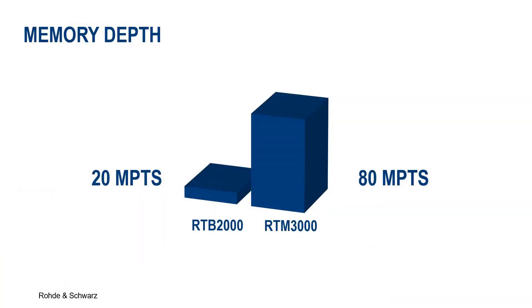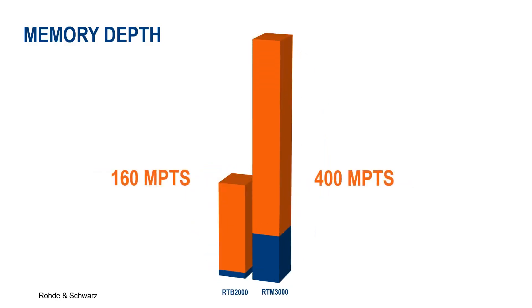Also, the 80 MPTS memory depth of the RTM3000 may be the better choice compared to the RTB2000's already impressive 20 MPTS memory depth. For both instruments though, history and segmented memory mode options are available, which will allow you to scroll through and analyze past acquisitions. This increases the memory depths to 160 MPTS for the RTB2000 and 400 MPTS for the RTM3000, which helps when capturing longer time periods of serial bus data.